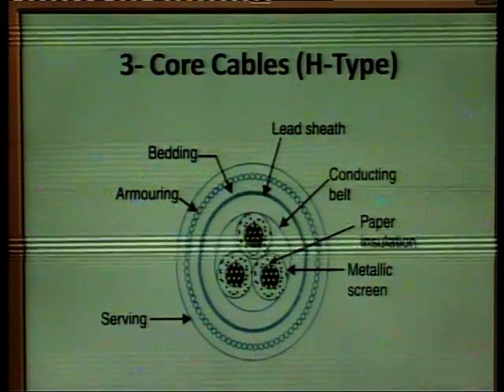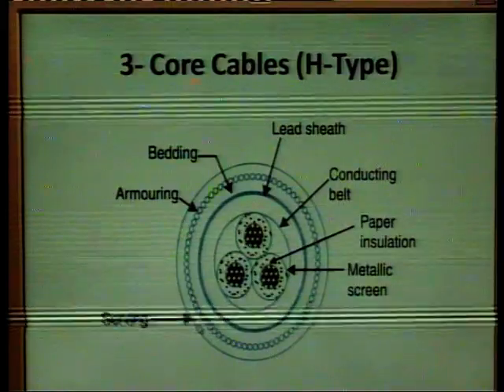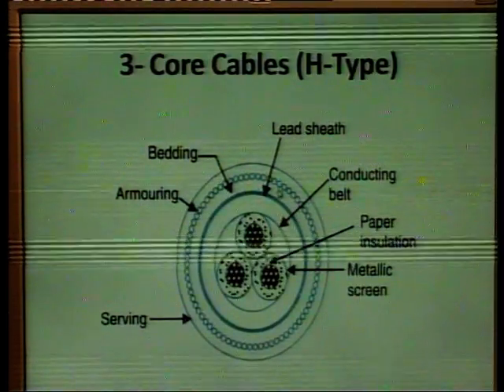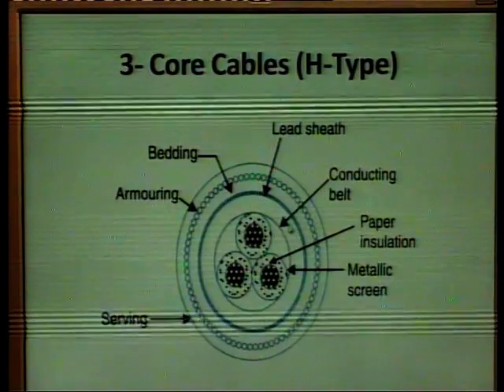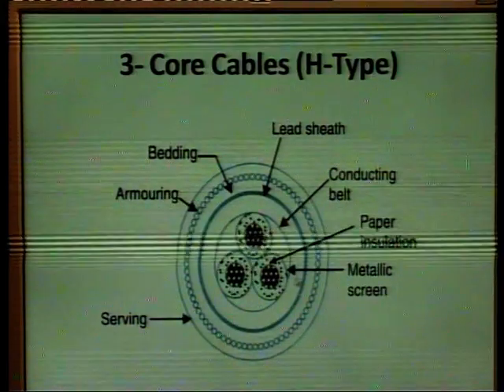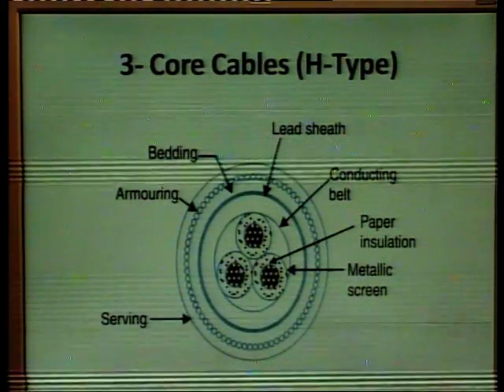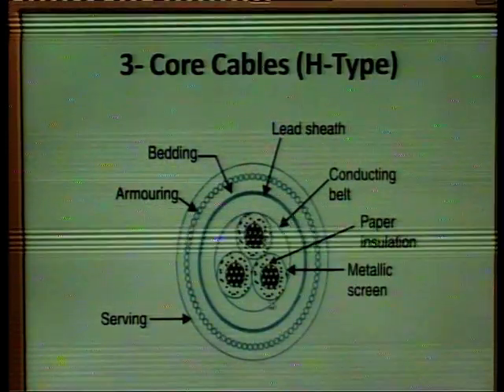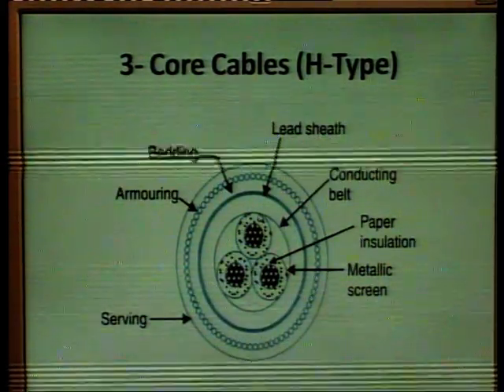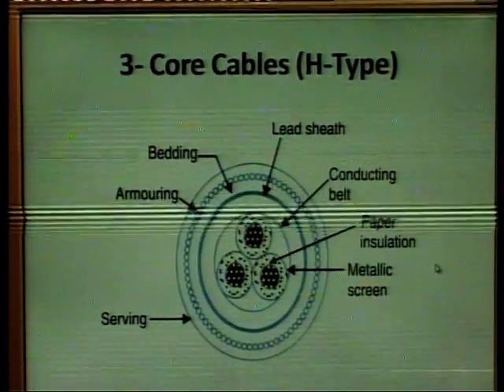So we can see this is the 3-core cable of H type. We can see the various parts. This is the outermost part, the serving, then the armoring, bedding, lead sheath, conducting belt, and this is the paper insulation, and this is the metallic screen. The paper insulation is there around all the 3 conductors, then it is kept in the conducting belt, then the lead sheath, bedding, armoring and serving. So this is the diagram of the H type 3-core cable.